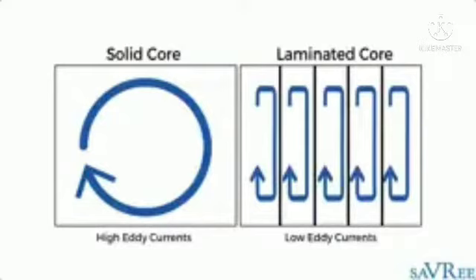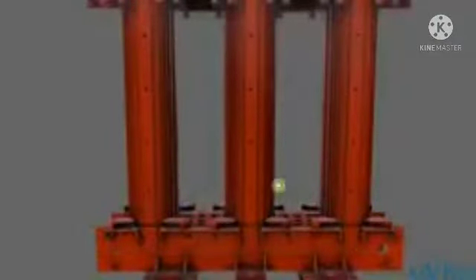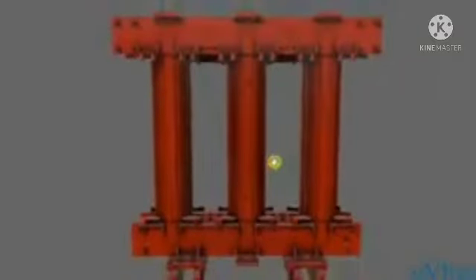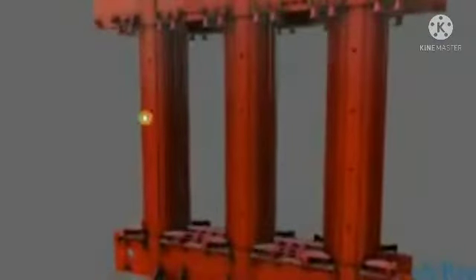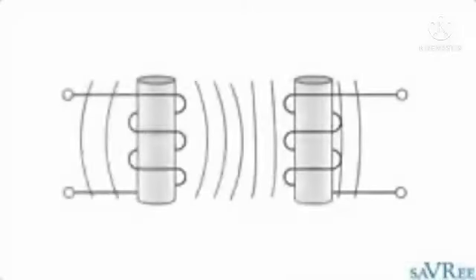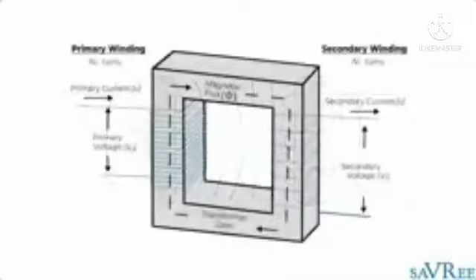So we'll clamp all of the metal sheets together to form a limb, and then we'll clamp the metal sheet pieces together to form the yokes, that is to say the top and the bottom of the transformer core. Now each of the sheets is insulated from its neighbour, and the reason we do this is because we want to completely insulate or isolate each of these metal sheets in order that we reduce the eddy current and hysteresis losses. When we have electrical current flowing through the windings, and the windings wrap around each one of these limbs, then we create an electromagnetic field, and the core is going to become magnetized. The job of the core is to direct this magnetic field in order that we can get a high magnetic field density or magnetic flux. So that's what the core is doing.